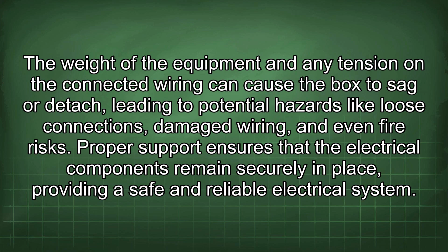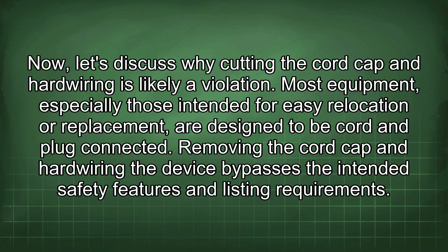Now let's discuss why cutting the cord cap and hardwiring is likely a violation. Most equipment, especially those intended for easy relocation or replacement, are designed to be cord and plug connected. Removing the cord cap and hardwiring the device bypasses the intended safety features and listing requirements. Here's why this is generally not permitted, and how to determine if it is.